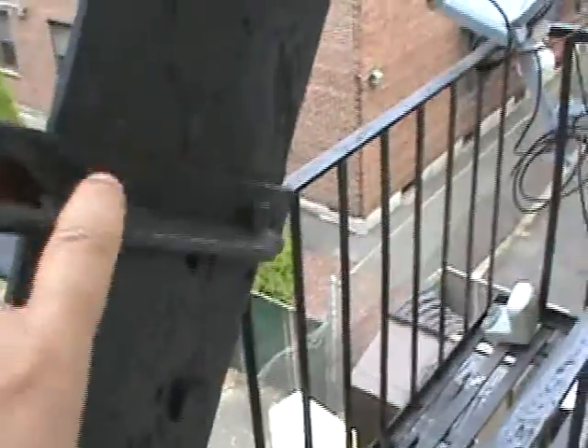NFPA code and guidelines require that the fire escape be load tested and/or other evidence of strength. This fire escape right now cannot be load tested in the as-is condition. It has a life safety emergency, and it needs 100% of the entire superstructure rebolted because you've got rust in every connection. So, all original hardware. No evidence of maintenance anywhere.